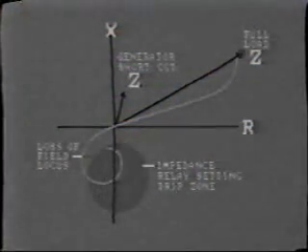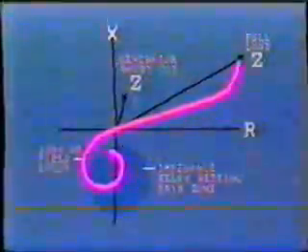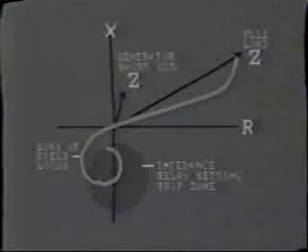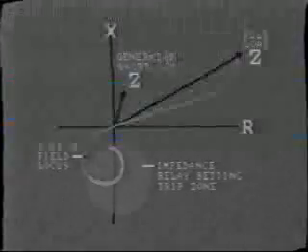The preferred method is to install an impedance relay, which compares the state of voltage and current. During normal, full load operation, the impedance will be out here. A short circuit on the generator terminals will bring the impedance to this point. However, if a loss of field occurs, the measured impedance would move usually into the fourth quadrant due to the import of reactive power. Consequently, the loss of field impedance relay is set to operate in this zone.